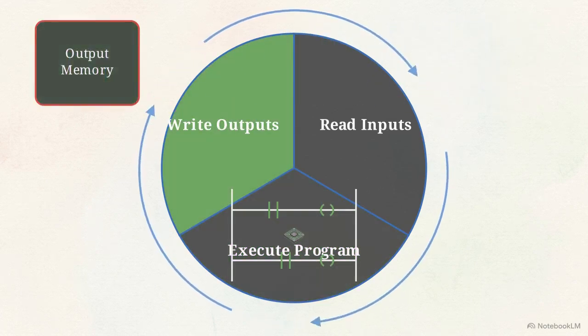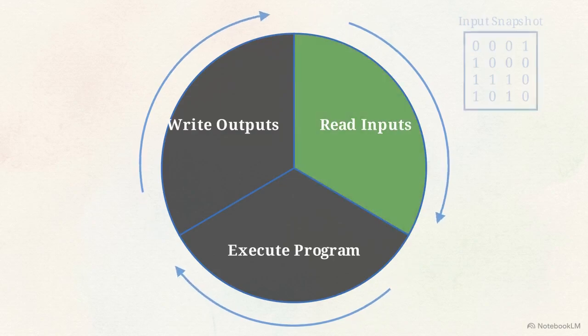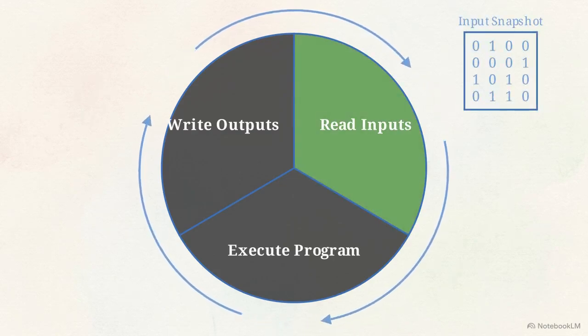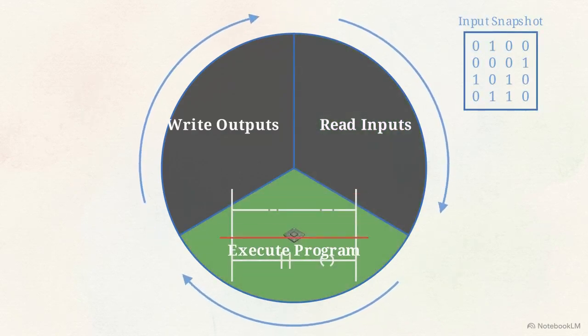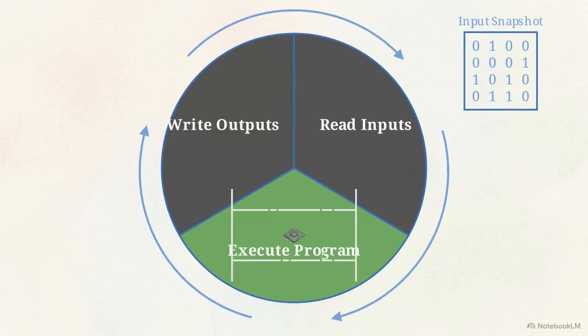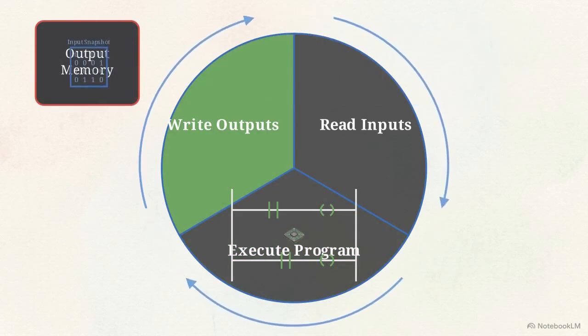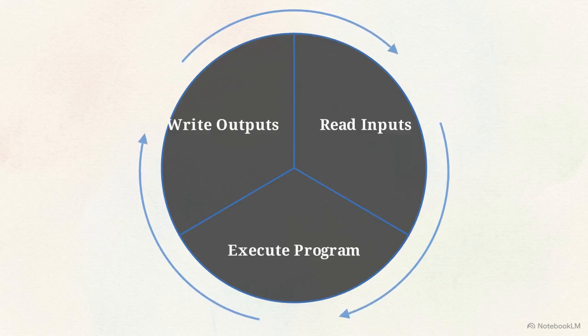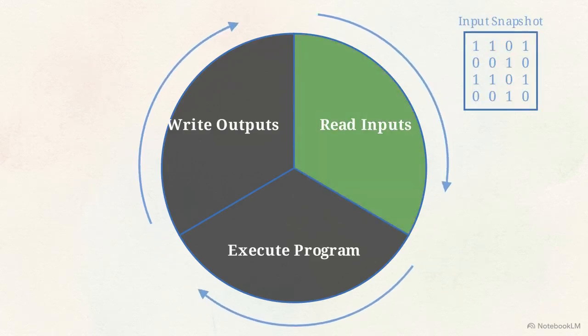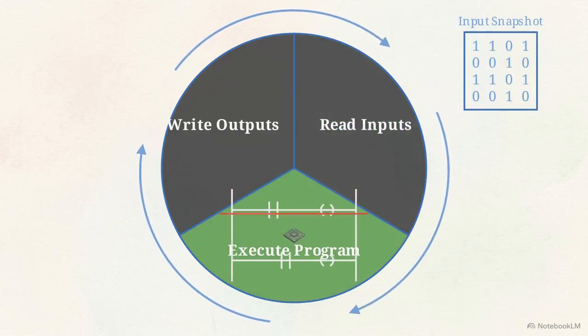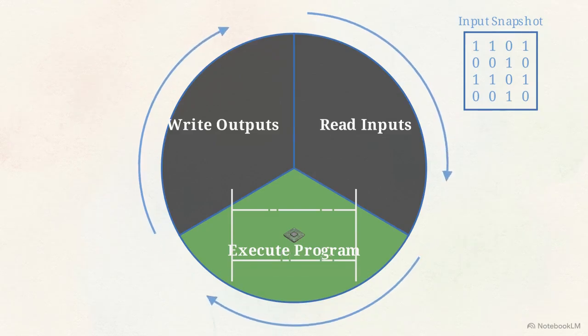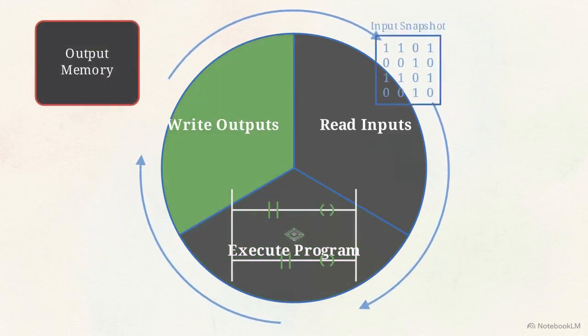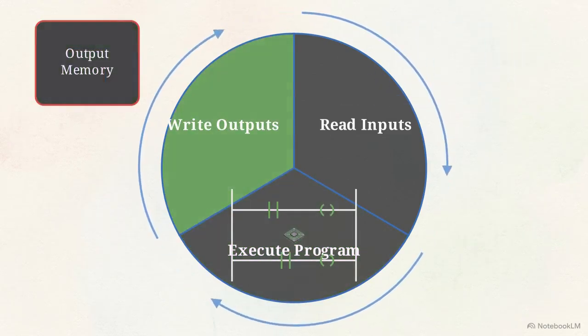Step 1. The CPU reads the physical states of every input terminal simultaneously, takes a frozen snapshot of those values, and locks them into memory. Steps 2 and 3 happen against that frozen snapshot. The CPU runs the ladder logic from top to bottom, calculates the required results, and then universally writes all the new states to the output terminals at the exact same time.